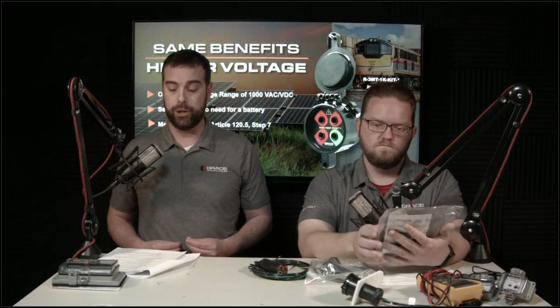Moving on from the Check Volt solution, we also launched our new 1000 volt safe test point device. This is a great solution that allows electrically qualified workers an alternative to using an adequately rated portable test instrument, letting them keep their enclosure door closed while testing and verifying whether power is present or that they've truly isolated the power, performing an absence of voltage test. Let's pop that up and give a quick visual of the 1K, the 1000 volt safe test point device.